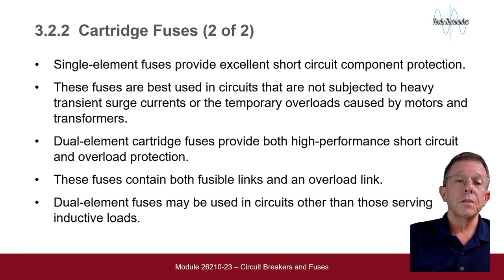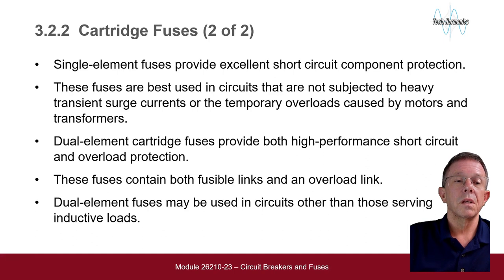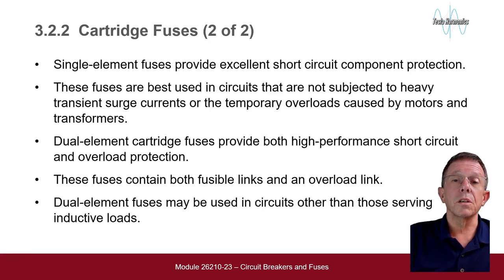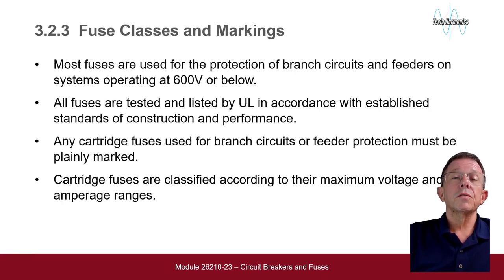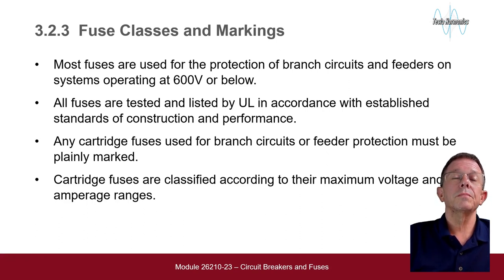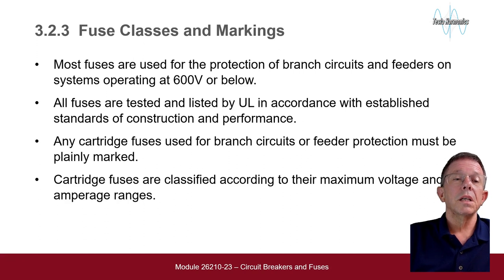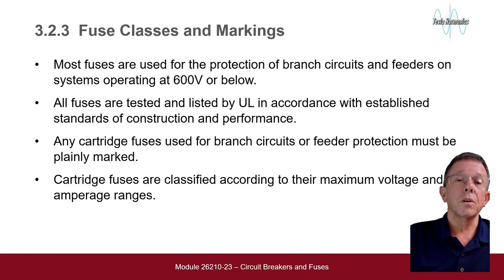Dual element cartridge fuses provide both high performance short circuit and overload protection. These fuses contain both fusible links and an overload link. Dual element fuses may be used in circuits other than those serving inductive loads. Most fuses are used for protection of branch circuits and feeders on systems operating at 600 volts or below. All fuses are tested and listed by UL in accordance with established standards of construction and performance. Any cartridge fuse for branch circuits or feeder protection must be plainly marked, and cartridge fuses are classified according to their maximum voltage and ampere rating.